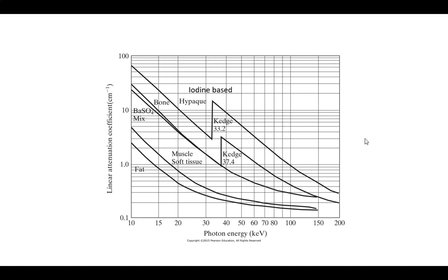As the linear attenuation goes down, it's interacting less, i.e. higher energy stuff, you can see the attenuation coefficients are smaller, therefore it does not slow things down as much when it's high energy. That's why we really can kill off the low energy stuff, because remember it was useless. If we don't filter it out, it's just going to end up inside the person, dose with no benefit.